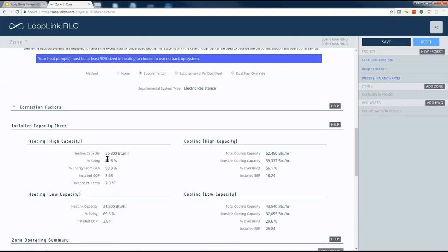And generally speaking, what I try to do when I'm designing a system is shoot for about 75 to 80% sizing. Because if you take a look here, 80% sized relative to the peak heating load, but we're still getting nearly 99% of the energy from the Geo unit, and the balance is being made up by our supplemental electric resistance. So we're not paying a whole lot of penalty right now for backup heat just by being undersized. But now take a look at our part load cooling capacity here, 30% oversized relative to the peak cooling load. A slightly better fit for this system.